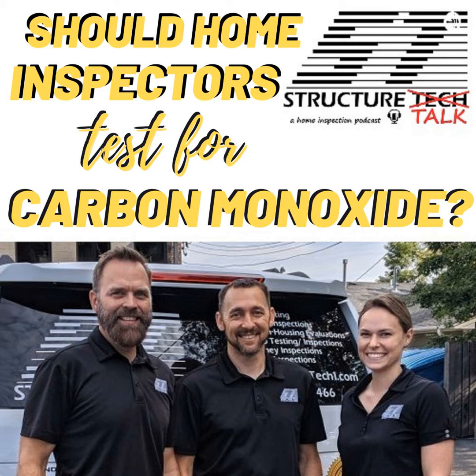That's right. Now, I've heard other HVAC contractors, Reuben, what do you think about this? Taking measurements across the diameter on the inside of the flue and taking the highest measurement. But I've always just stuck it right in the middle of the flue, perpendicular, making sure that it's exactly perpendicular with the flow of the exhaust gas. Well, it depends. How's that for a good answer, Tess? Yeah, that's your favorite. Sounds like a perfect answer for Tess.